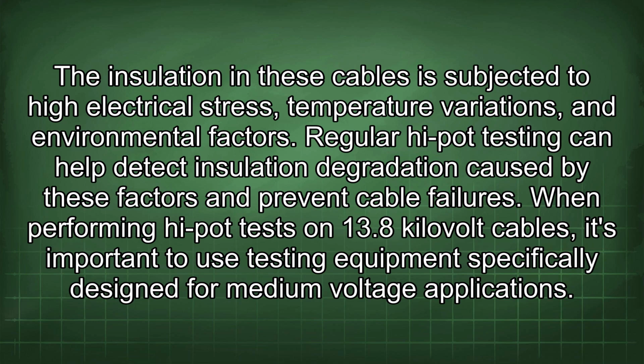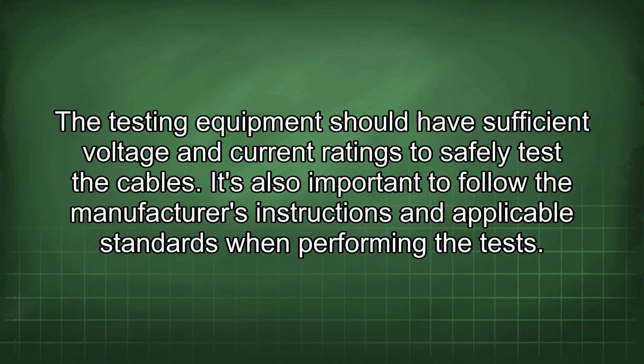When performing hi-pot tests on 13.8 kV cables, it's important to use testing equipment specifically designed for medium voltage applications. The testing equipment should have sufficient voltage and current ratings to safely test the cables. It's also important to follow the manufacturer's instructions and applicable standards when performing the tests.